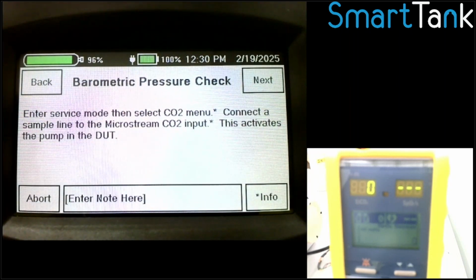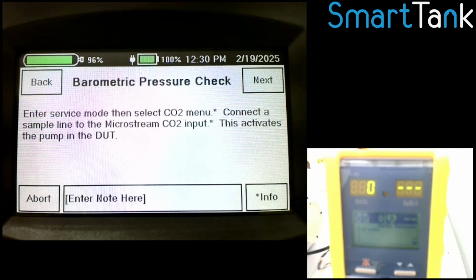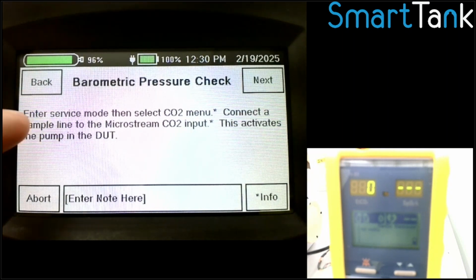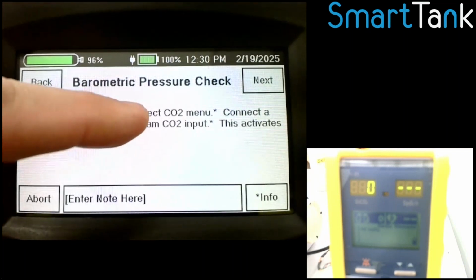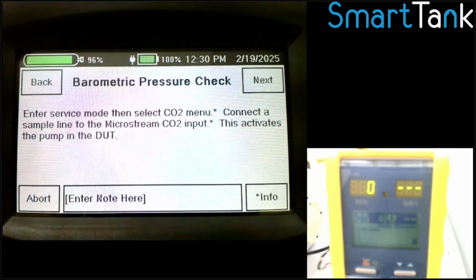And now we get to the very first test. There's 3 tests in the sequence, the barometric pressures being the first one. And it's telling me to enter the service mode, then select CO2 menu. Now, if you're not familiar with how to do this, you might be like, oh, how do I do that? Well, these little stars on here say, hey, there's more information.